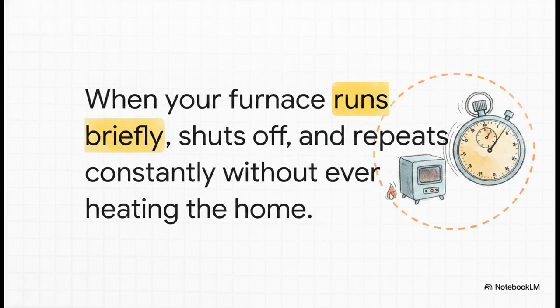Now flip the calendar to winter, and you might face the exact opposite nightmare: short cycling. This is when your winter furnace runs for maybe 2 minutes, shuts off, and repeats constantly without ever actually heating the home. It's incredibly frustrating, often caused by a failing flame sensor, a cracked heat exchanger, or—super common in homes built during Plainfield's rapid housing booms—simply a unit improperly oversized for your home. It wastes a ton of energy and rapidly accelerates wear and tear on your gas valves and igniters.